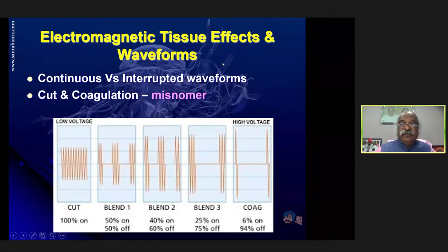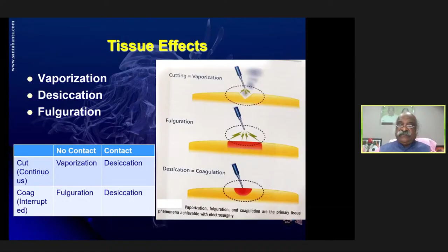Now let us go to the tissue effects. What are the tissue effects? There are tissue effects like vaporization, desiccation, and fulguration. And we have two modes, non-contact mode or contact mode. In non-contact mode, in a cut or continuous current, vaporization occurs. In contact mode, there is desiccation. In coagulation mode, with interrupted current, we want fulguration in the non-contact mode and desiccation in the contact mode. Whatever it may be, the tissue effects vary from vaporization, fulguration, and desiccation at the tissues by the electrode.